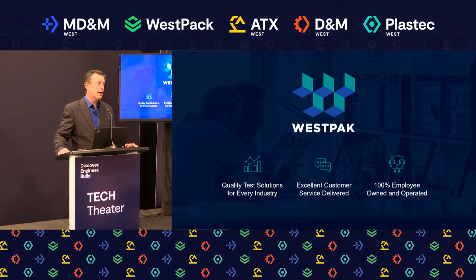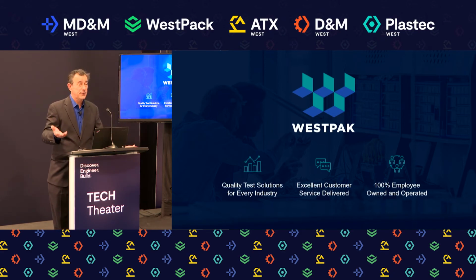It is making recommendations for when you need to use humidity, and that really follows what materials you're going to use in your product. Again, it's more product focused because the packaging materials are not really sensitive to moisture. So it's not prescribing it, but it's helping guide you. It's giving you a range: if you don't know, here's a range of humidity to use, here's a temperature. And the temperature says 50 degrees C.